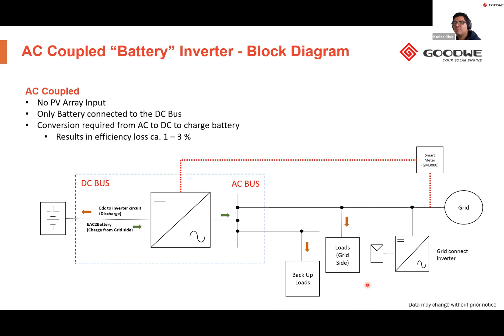This just gives you a quick overview of the advantages and disadvantages of each system. I won't go into too much detail here, but one of the main disadvantages of an AC coupled system, especially in a grid failure scenario, is that when the grid is down, the grid connect inverter will disconnect itself from the circuit due to its anti-islanding features. So in these situations, in a backup mode, the loads will only be powered by the battery. Whereas, as you can remember from my previous slide, in a grid failure situation, the loads will continue to be powered by both the PV and the battery. So that's just one disadvantage.